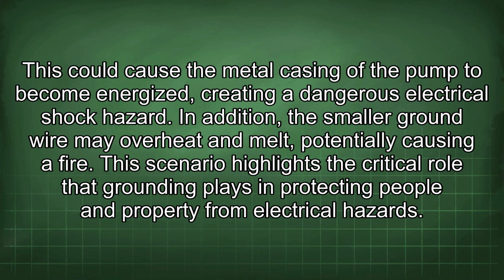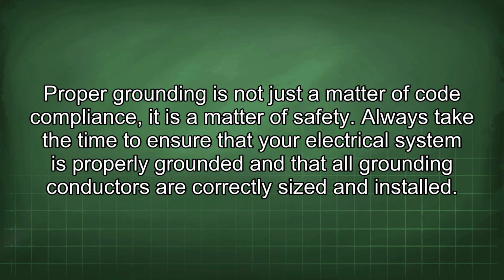In addition, the smaller ground wire may overheat and melt, potentially causing a fire. This scenario highlights the critical role that grounding plays in protecting people and property from electrical hazards. Proper grounding is not just a matter of code compliance, it is a matter of safety. Always take the time to ensure that your electrical system is properly grounded and that all grounding conductors are correctly sized and installed.